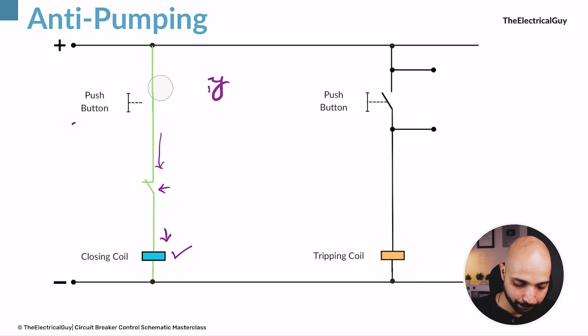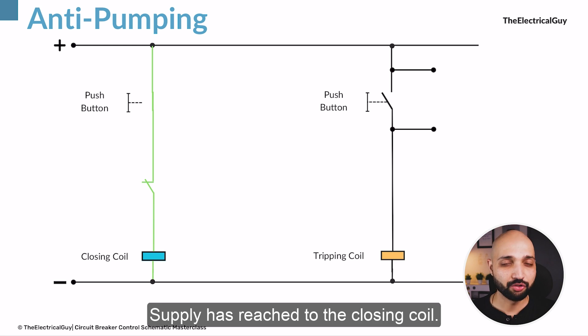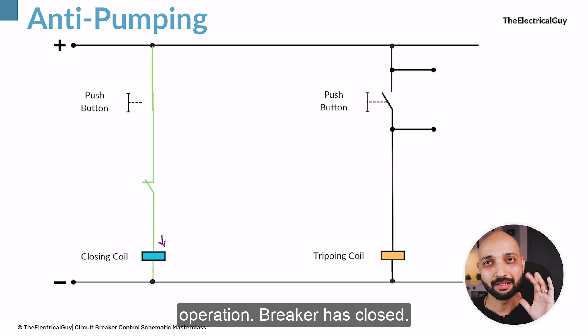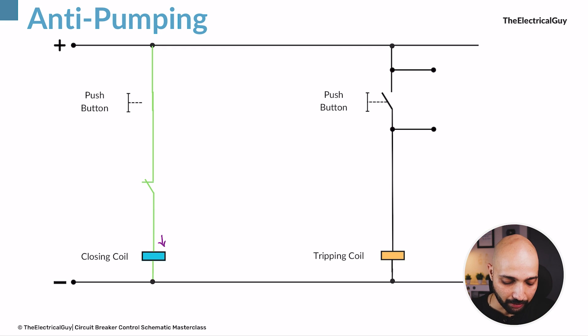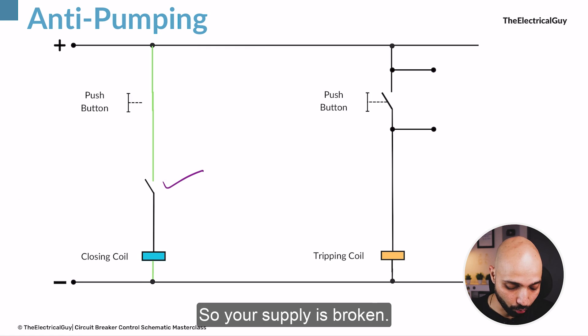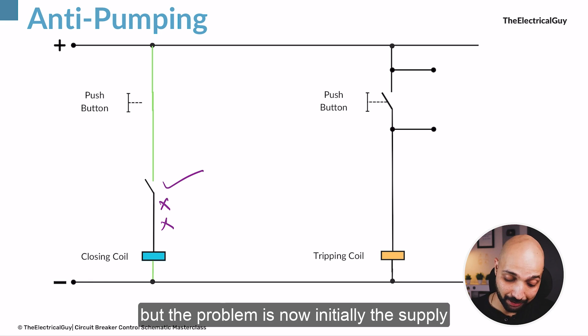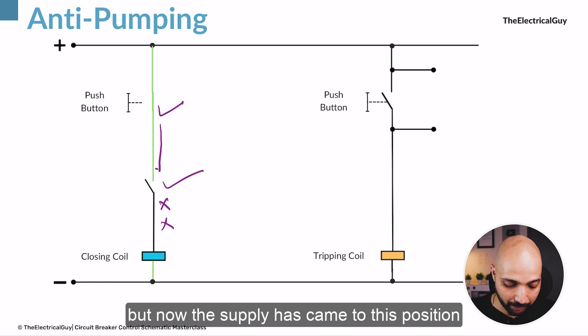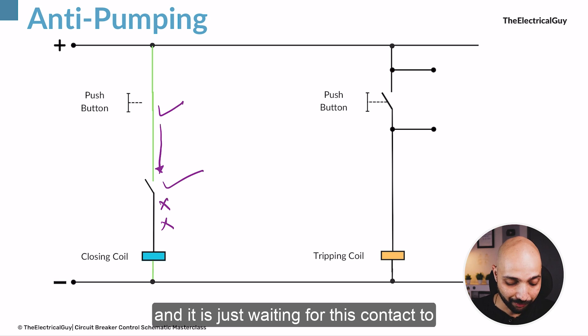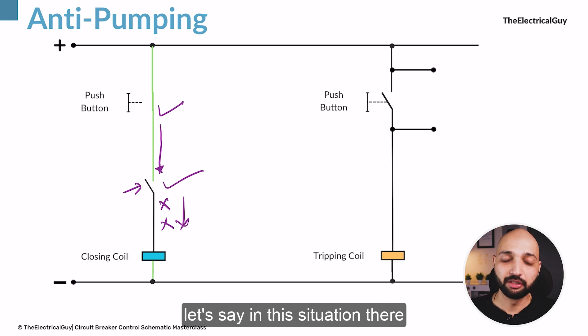So let me explain: you pressed the push button, supply reached the closing coil, the closing coil initiated the closing operation, the breaker closed. The moment the breaker closes, the NC contact opens — so the supply is broken and the closing coil is no longer getting supply. But the problem is the supply was held at the faulty push button and is now sitting just before this NC contact, waiting for it to close again. The moment this NC contact closes again, supply will reach the closing coil.